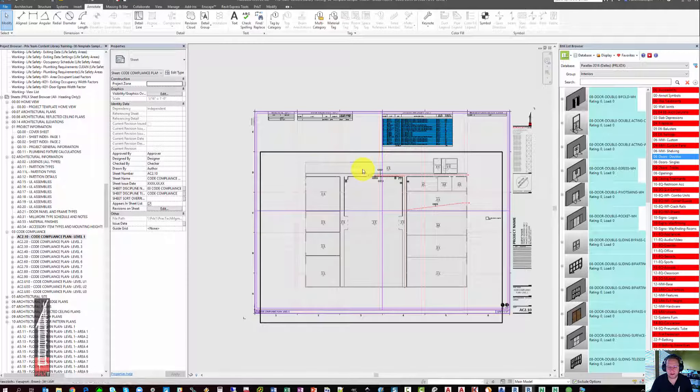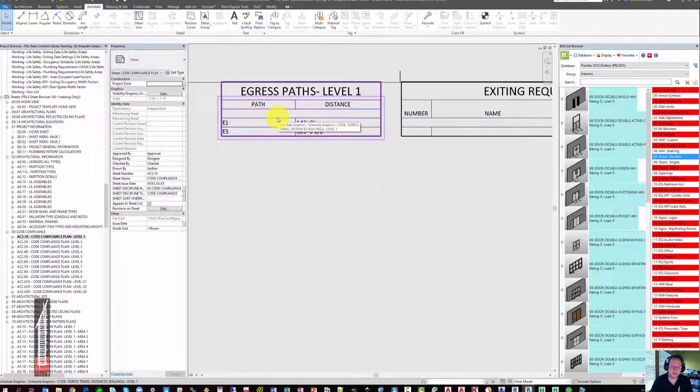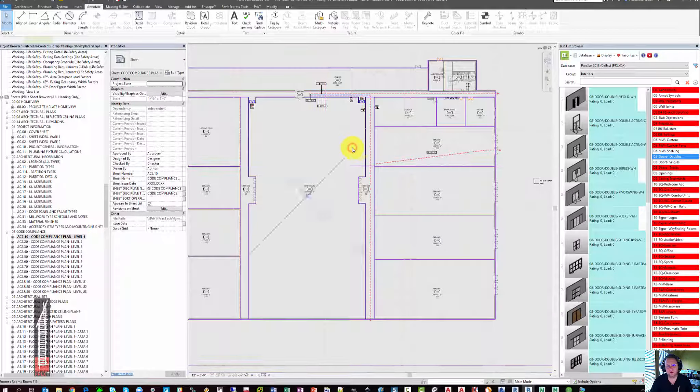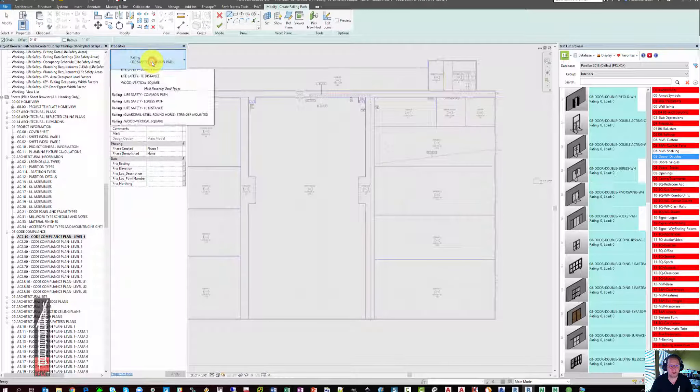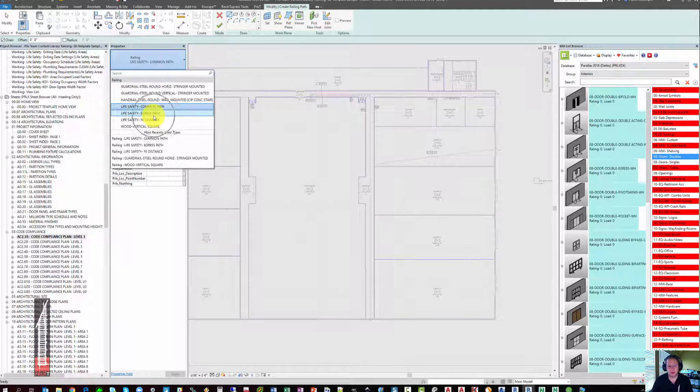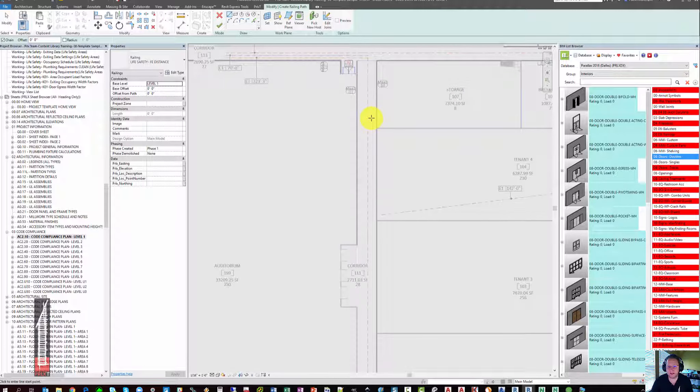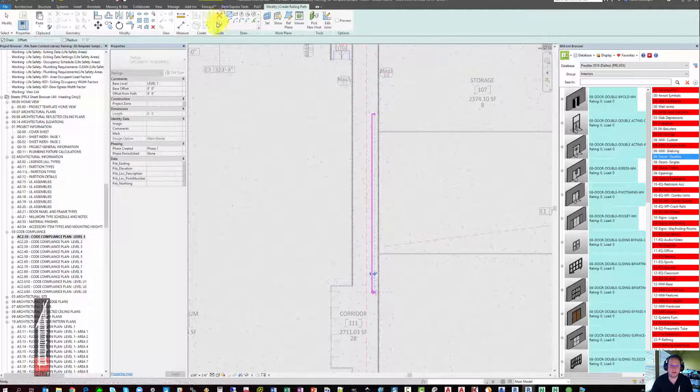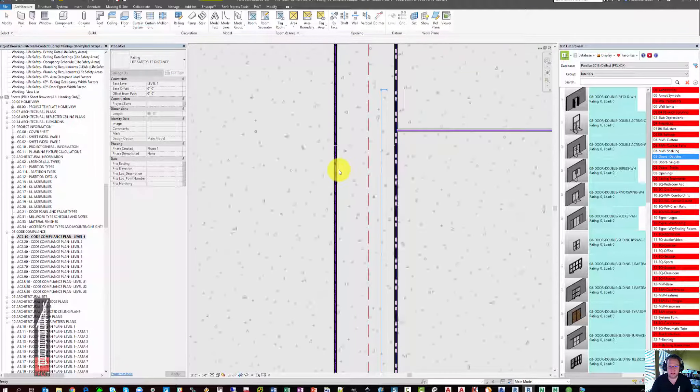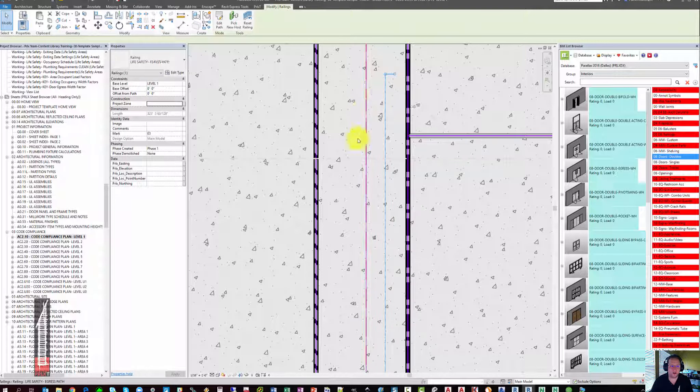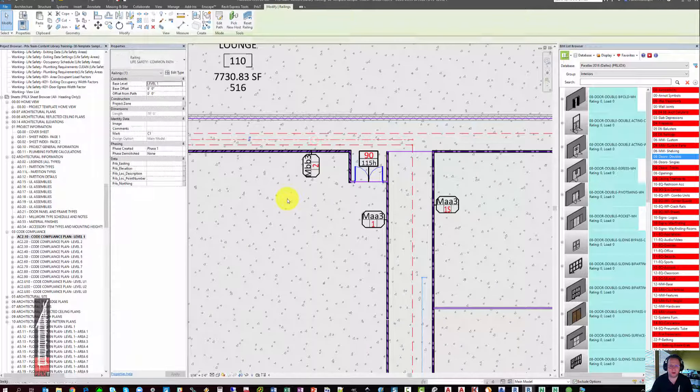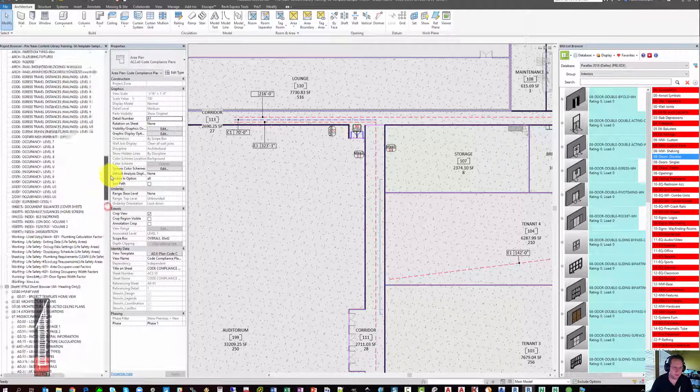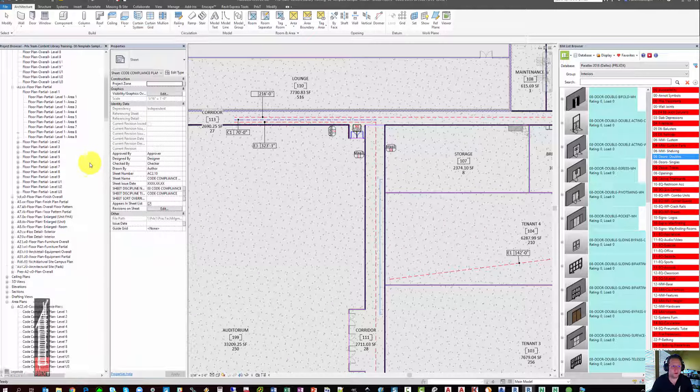The last schedule that exists on the code compliance plan is egress travel paths. Travel paths in the parallax template for code compliance are done using the Revit railing tool. If you go to the railing tool, you'll notice that there are several railing types that are called life safety. There is one for common path of travel, there is one for egress paths, and there is one for paths between fire extinguishers. If you wanted to mark that distance on a plan, you could draw the distance between your two fire extinguishers using the FE distance. And you'll see that all three paths are fire extinguishers distances, our egress paths, and our common paths of travel all get different line styles and different colors.